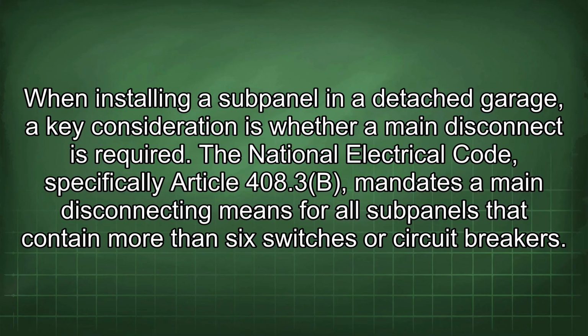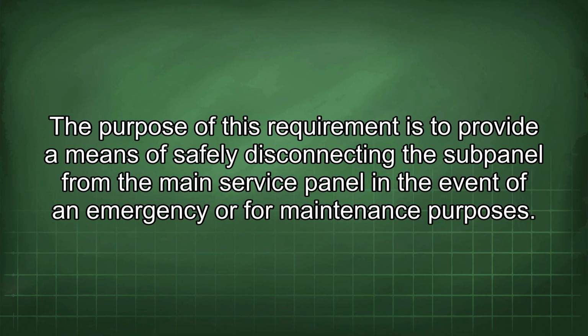When installing a subpanel in a detached garage, a key consideration is whether a main disconnect is required. The National Electrical Code, specifically Article 408.3(B), mandates a main disconnecting means for all subpanels that contain more than 6 switches or circuit breakers. The purpose of this requirement is to provide a means of safely disconnecting the subpanel from the main service panel in the event of an emergency or for maintenance purposes.